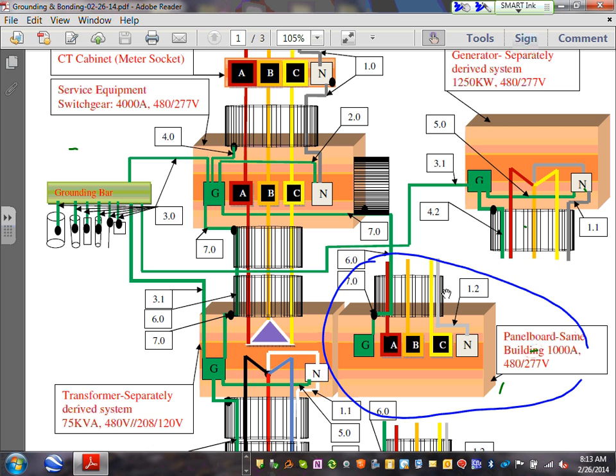I need to size, in terms of grounding, the following. I need to size the grounded conductor that's coming from this switch gear here. So it's coming from the switch gear to this switchboard, or switch gear to this panel board. And I need to also size number 6. Can you see number 6 and number 7? Number 6 is called the equipment grounding conductor. That's the wire that comes from the fixture to that panel. The terminology, guys, is so important, because if you don't know this terminology, you will never understand grounding and bonding. Equipment grounding conductor. And then that little connection here, can you see that little connection bonding the conduit? They call it bonding the conduit. That's called the equipment bonding jumper, load side. So I have 7, equipment bonding jumper load side, and 6, equipment grounding conductor, and 1.2 is the grounded conductor. So let's go size these. Now this is a sub panel. Everybody can see that this is the sub panel. We have a sub panel right here, right? Makes sense? All right.